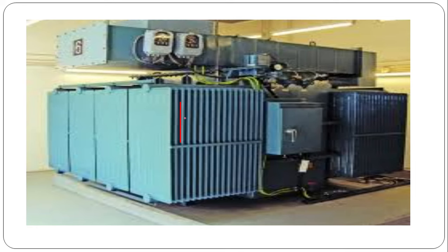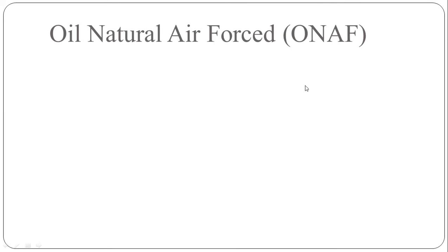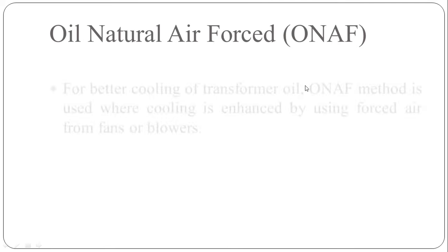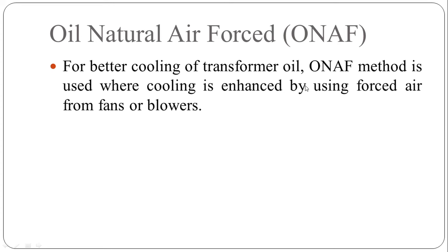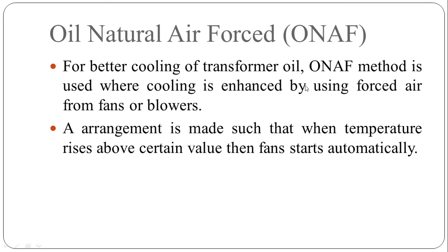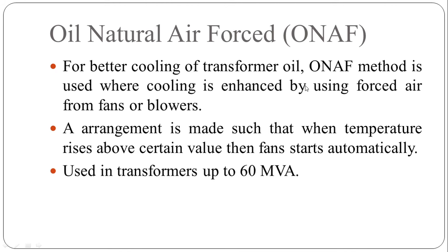This is the transformer with oil natural air natural (ONAN) cooling. The stack of tubes is called the radiator and is connected to the tank of the transformer. The second scheme is oil natural air forced (ONAF) cooling. For better cooling, ONAF method is used where cooling is enhanced by forced air from fans and blowers. An arrangement is made such that when temperature rises above a certain value, fans start automatically. It is used in transformers up to 60 MVA.